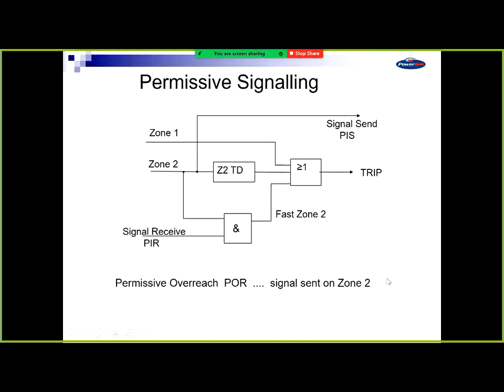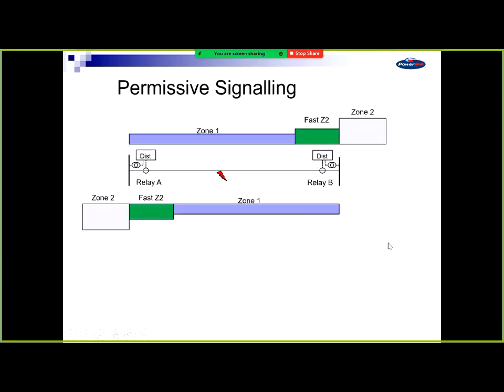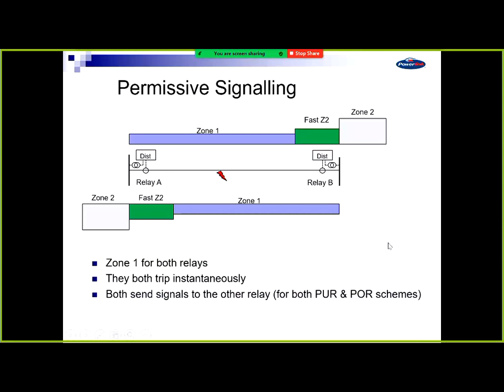And the previous one here, you saw for permissive underreach, the signal gets sent on that zone 1. Permissive overreach, the signal gets sent on that zone 2. The PIS stands for permissive intertrip send. The PIR stands for permissive intertrip receive. So a fault in the middle of the feeder, both relays see it in zone 1, they both trip instantaneously, and they both send signals to each other for permissive underreach and overreach. So a zone 2 always encompasses the zone 1 and is just bigger. It's not an area on its own. So if you turned off zone 1, zone 2 would cover the whole feeder.